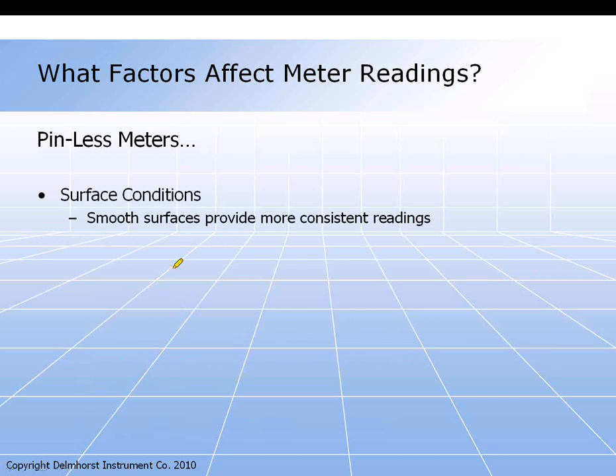On pinless meters, the surface conditions play a big role in the meter readings, and the smoother the surface, the more consistent your reading is going to be. And this is really a function of the pad or the sensor plate making good contact with the material that you're testing. If it's a smooth surface, the pad is going to make nice firm contact, and you're going to have more consistent and more uniform readings. If you've got a little rough, whether it's a textured wallpaper or paint, or even a little bit of a rough concrete surface, when you place the meter on that surface, there are some air pockets created because of the unevenness in the surface, and that's going to give you typically a little bit lower reading, a little bit less consistency in the readings.